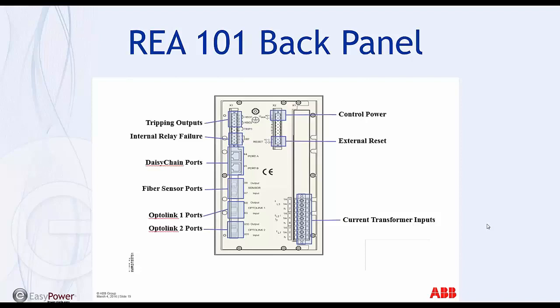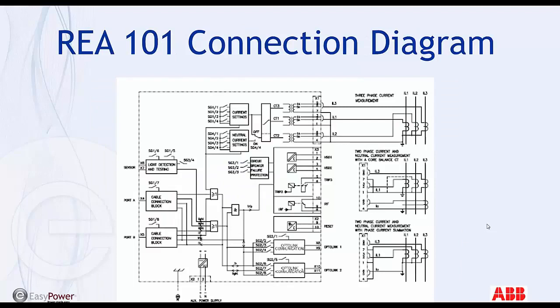This is a connection diagram for the main unit. There are connection diagrams for the extension units as well. We won't show those this time. This is very helpful as a troubleshooting tool. It can also help you predict how the system is going to behave. It tells you how the CTs can be connected. If you want to use ground, you can use a zero sequence. You can use the residual, or you can just have 3 phases. You can have a 1 amp or a 5 amp nominal. It shows all the switch settings here, which is helpful because it can tell you what information is passed back and forth between the main units or the main unit and the extension units.